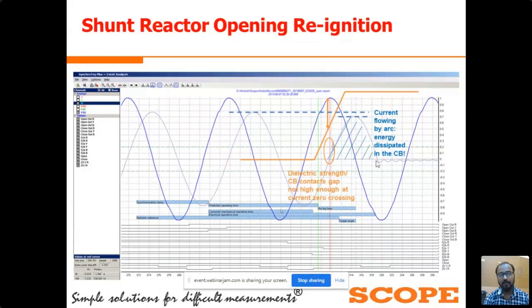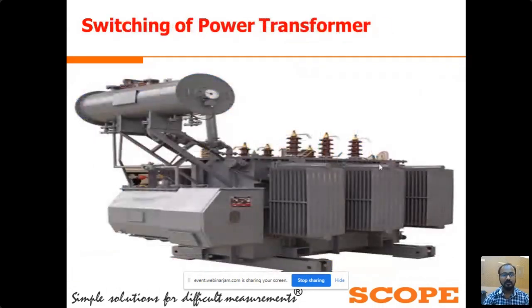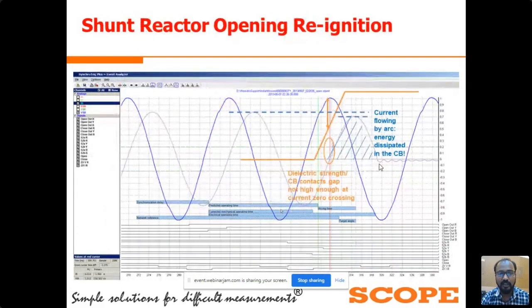From this operation we can see that if we do a reactor opening without any reference of system voltage, there is a chance of reignition of current between the CB contacts. By using the control switching device, we have completely eliminated the chances of reignition of system current between the CB contacts. Basically, these are the two strategies we use for shunt reactor application: we close the shunt reactor near the voltage peak points, and we open the CB contacts near current zero and in the reignition free window for the opening of the shunt reactor.